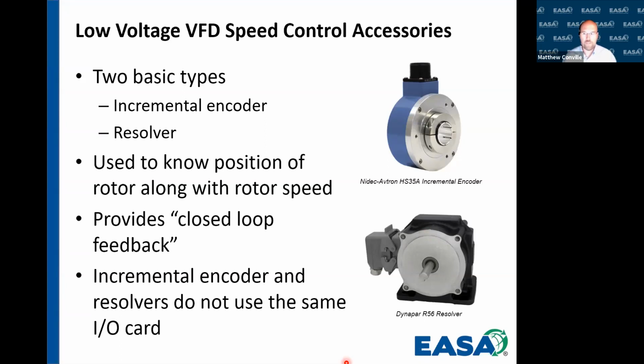What that means is the drive system almost always creates a motor model in most of the control methods. And there's a webinar that I did on that earlier this year. When we use these closed loop feedback devices, they're actually confirming to us where the rotor is, so that the drive system now has precise control of the ID and IQ current, so that we can develop the torque and speed that we want.